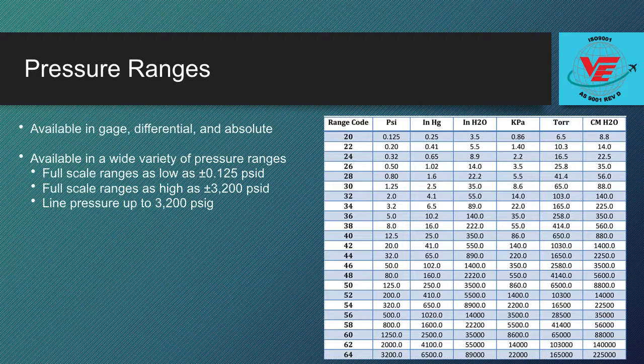There are 23 differential full-scale ranges for the P895, from 0.125 psid to 3,200 psid. In addition, every P895 can withstand line pressures of up to 3,200 psig. This means a low-range P895 can be used to measure small pressure drops in a system, even if that system is running at a high-pressure line.